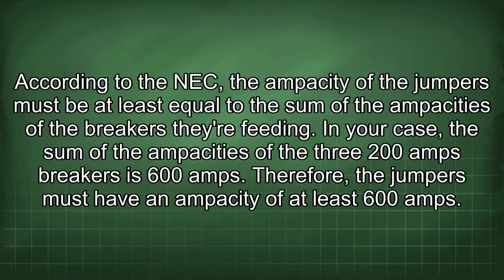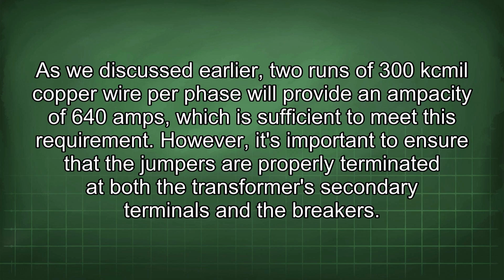In your case, the sum of the ampacities of the three 200 amp breakers is 600 amps. Therefore, the jumpers must have an ampacity of at least 600 amps. As we discussed earlier, 2 runs of 300 kcmil copper wire per phase will provide an ampacity of 640 amps, which is sufficient to meet this requirement.